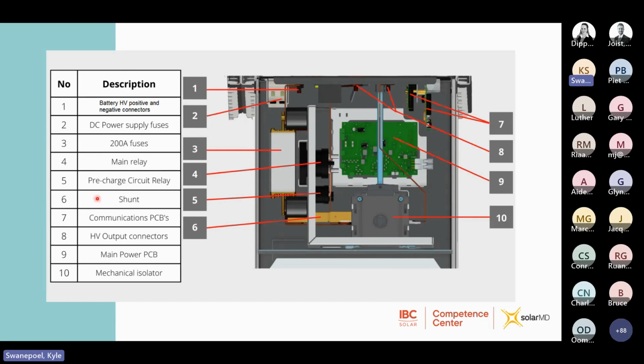Okay, cool. Then there is also a pre-charge circuit relay over here. The shunt, this is for measuring the current. So the current flow will be measured based on the voltage drop between point A and point B. And that's how that will be calculated. The communications PCB, so this is where your CAN bus and your RS485 communication will happen, as well as Ethernet communication. And then your HV output connectors sit over here.